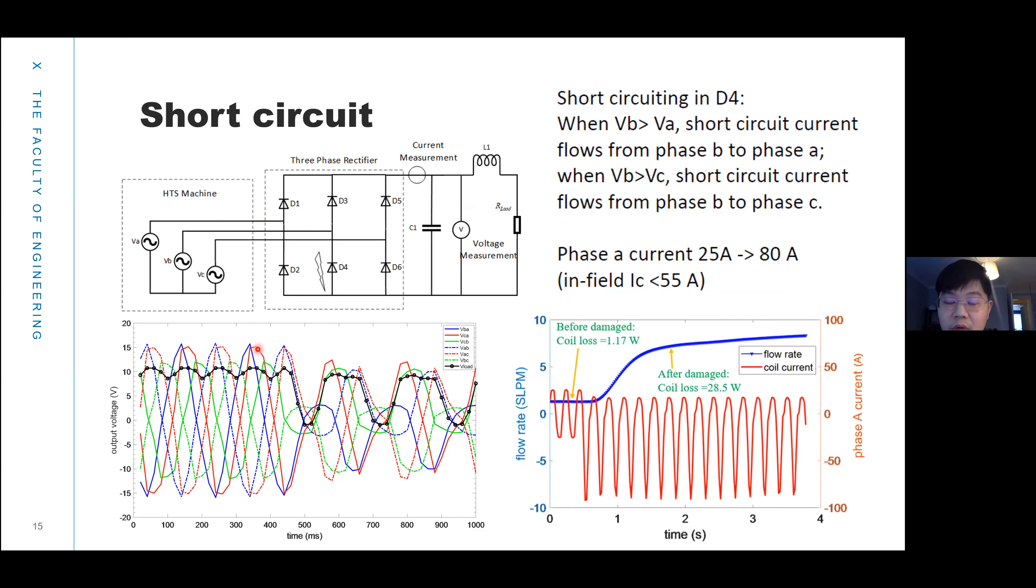After the short circuit test, we found the transport current in the HTS coil increased from 25 amps to 80 amps. The critical current for this coil is only 55 amps. We observed the flow rate. This is the measurement before the short circuit event, and the coil loss is 1.17 watts. After the short circuit event, there is around 90 amps in the HTS coil. After the short circuit event, the coil loss is above 28.5 watts, so it's around 28 times higher than before.